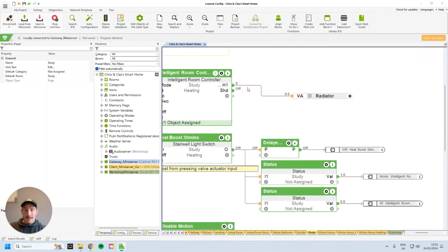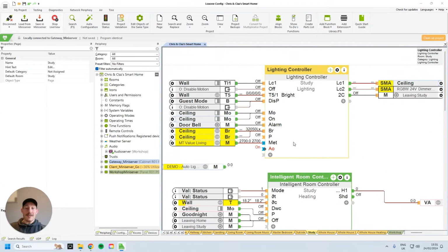If we move into the lighting controller here, this is the main control for the lighting, as you probably noticed. You can see that ceiling MO is the motion sensor. If I stand still, there you go, it's just gone off. If I then move, that triggers the motion sensor, which can be used to extend the lighting if I'm still present in the room.